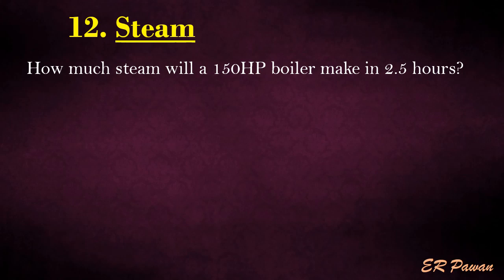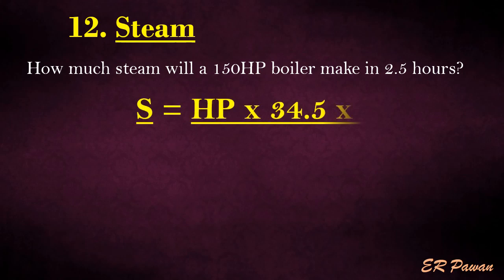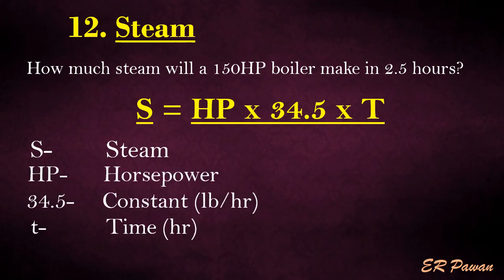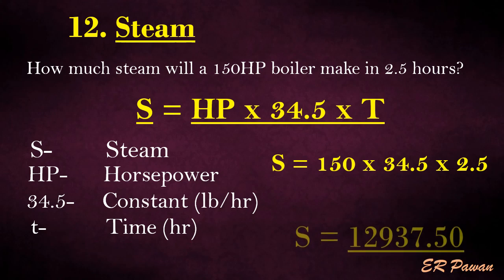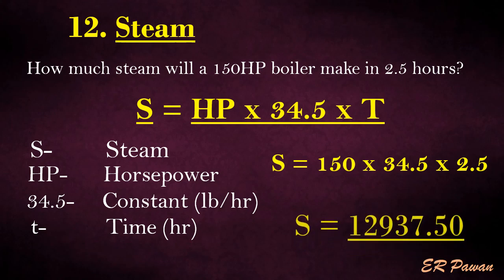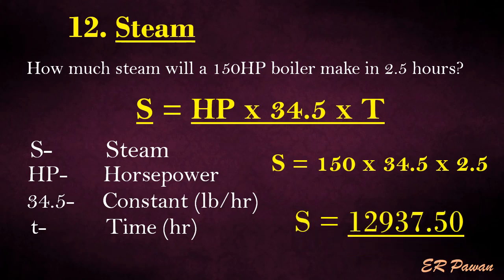Formula 12 — Steam. How much steam will a 150 HP boiler make in 2.5 hours? Steam equals horsepower multiplied by 34.5 multiplied by time, where 34.5 is a constant. Let's put the value in the formula.